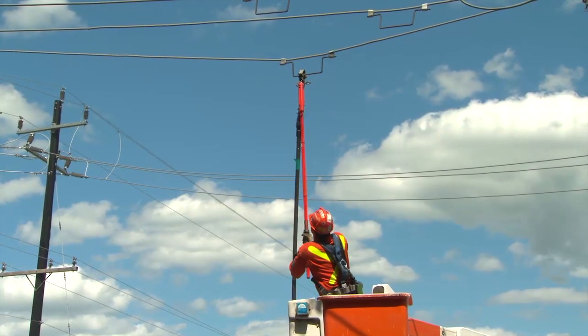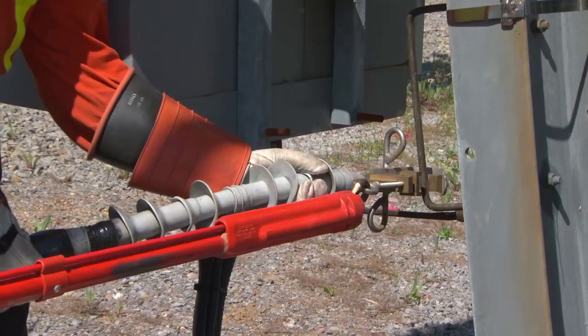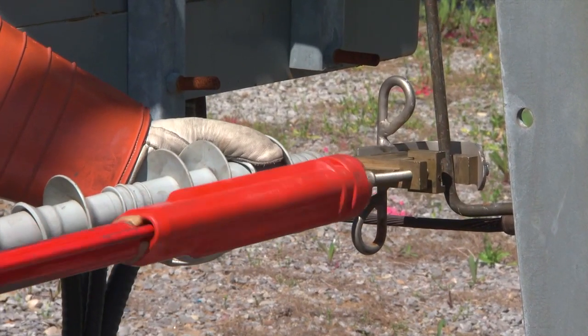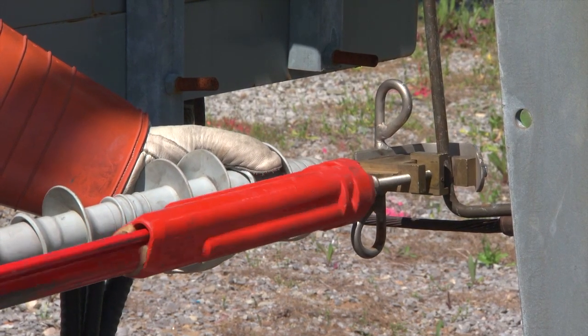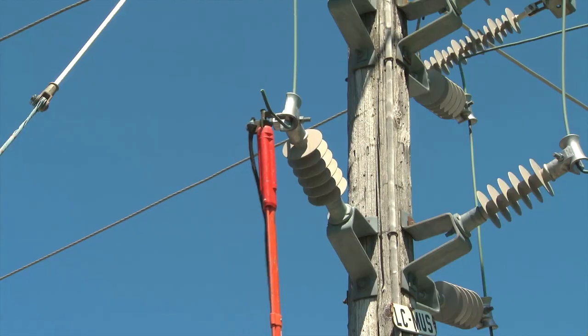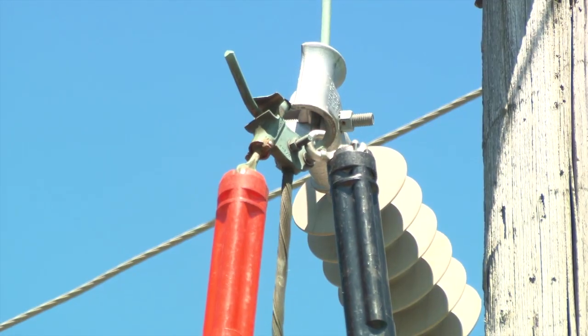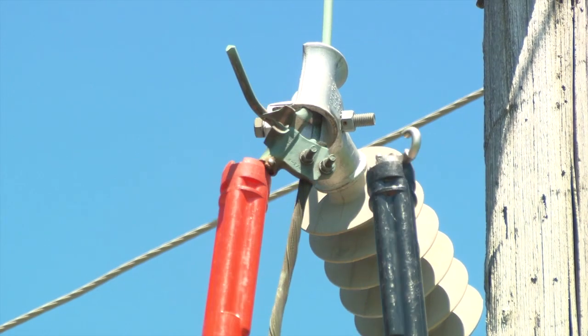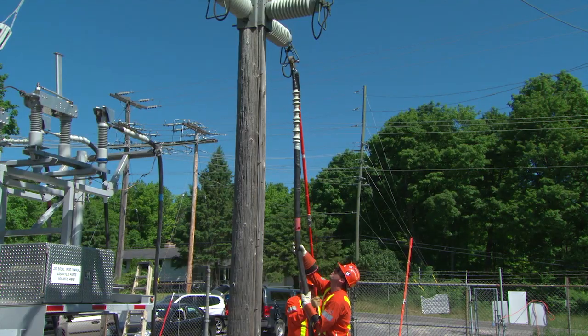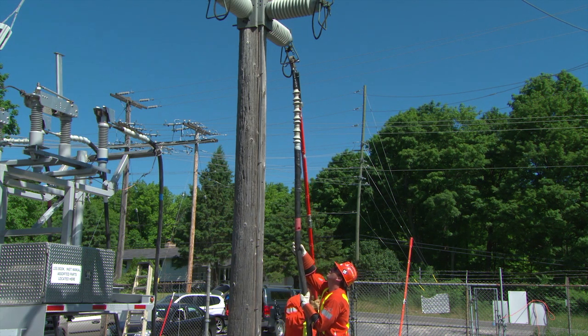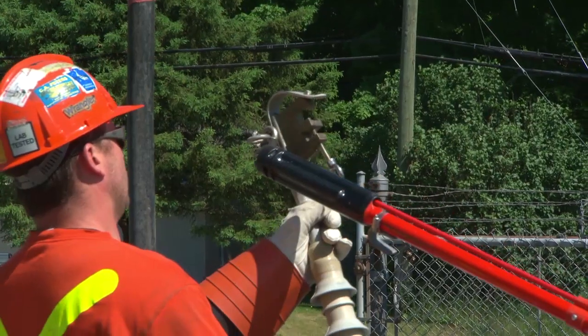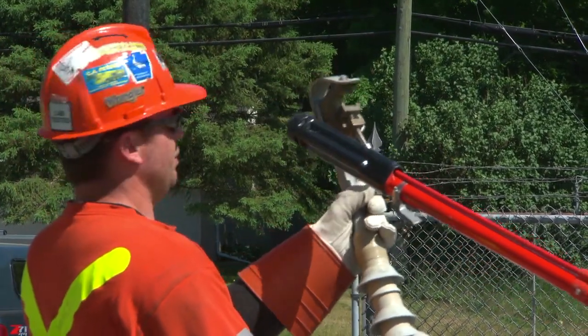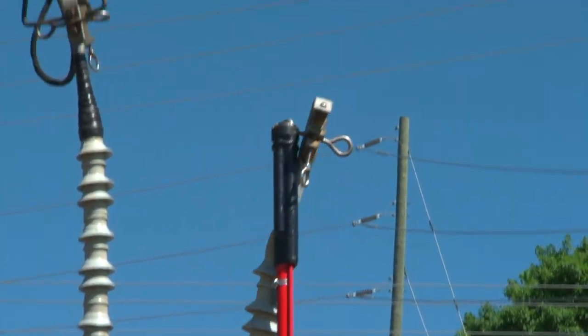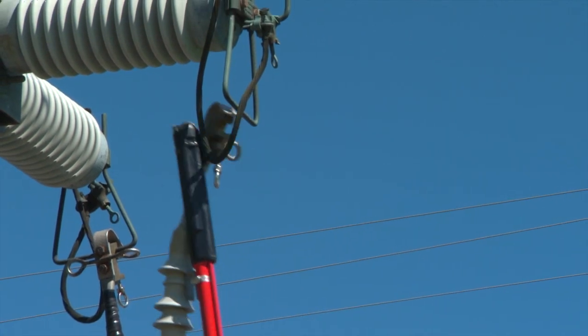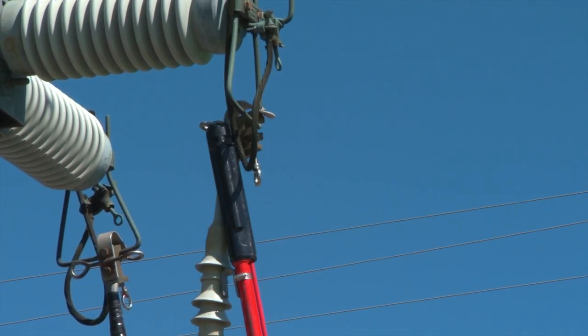Live line sticks are made of fiberglass reinforced plastic tubing with a unicellular foam core. The fiberglass tube structure gives them great strength with light weight. The foam core keeps them clean and moisture-free inside. MUS work requires the use of grip-all sticks and sectional sticks. Grip-all sticks operate live line clamps and are used to install and remove portable grounds, hang and remove work protection tags, hang and remove cables, or open and close switches, MSOs, or -LC and -BC jumpers. They come in different lengths, but the main sizes used for MUS work are 6 feet, 8 feet, 10 feet, or 12 feet.